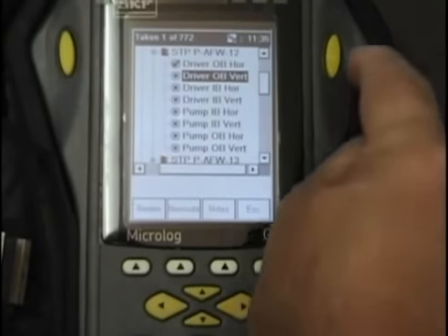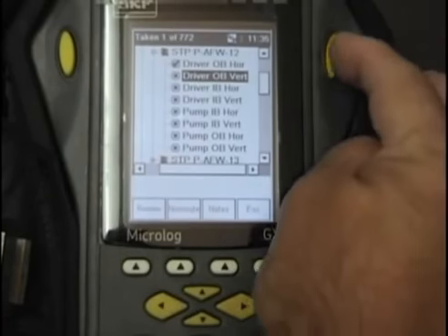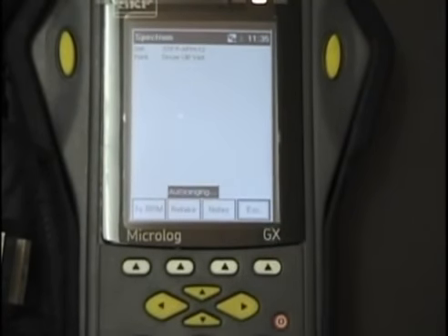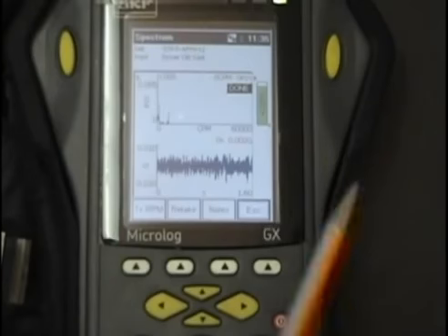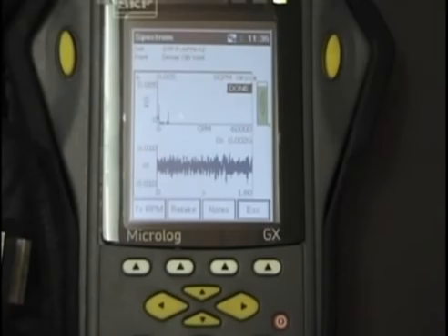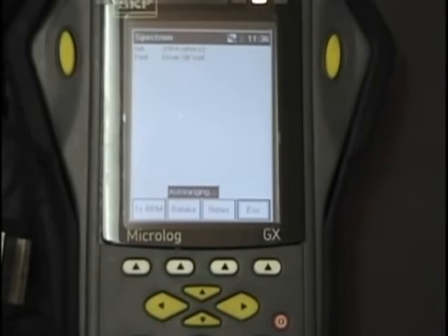Again, once you have the transducer on the correct blue dot, press the enter button. Again, it'll auto-range and collect data. Once it is finished, the done icon will appear. Again, this is the information you'll be writing down in the STP. If you feel that the data is in error, you can retake the data by hitting the white soft key below retake, and the data previously taken will be overwritten with the new data.